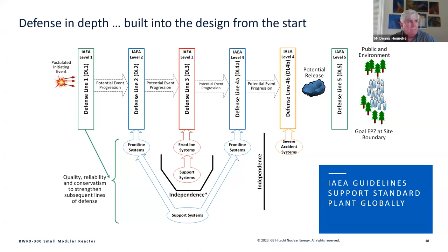or a safety-related function. Now, if you evaluate the safety analysis, what you're doing is analyzing these postulated initiating events with the plant response under defense line 1, which are the things that try to keep you operational, things that try to keep you from having an event by itself. But then that actuates defense line 3 systems, and you still have to meet your performance criteria utilizing defense line 3 systems. So that deterministic analysis still is a requirement, even under the LMP and IAEA risk-informed approach.